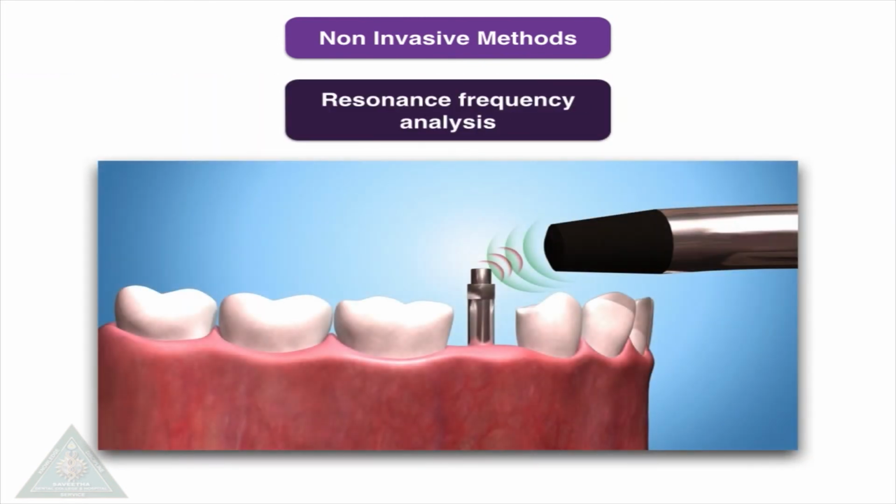The next is resonance frequency analysis. Two piezoceramic transducers are positioned either on the implant or the implant abutment. A computer-based measurement is then made in which a signal of 5 to 15 kHz is applied to the implant and the first resonance is measured. The implant stability quotient is rapidly determined within 5 seconds.